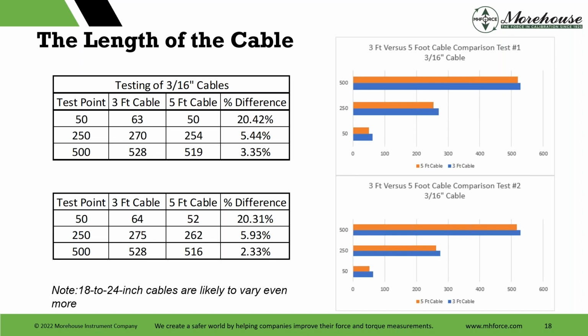So here we have a 3-foot cable, exact same test, right? Same machine used, the same tensiometer calibration method to compare the cables, made from the same material, and the method employed the clamp and adjust technique on these, right? Which kind of simulates dead weight, which means we load to, if it's 50, we probably load to 40 pounds of force, clamp it, and then adjust it in. For 500, we load to 460, clamp it, it shows 495, we adjust it in until it reads 500.